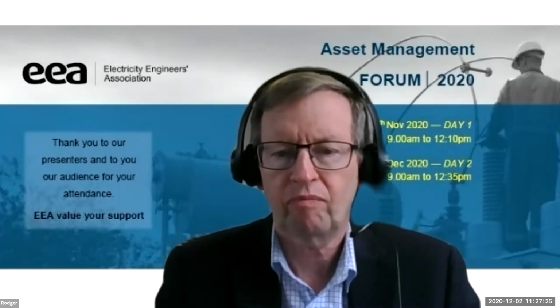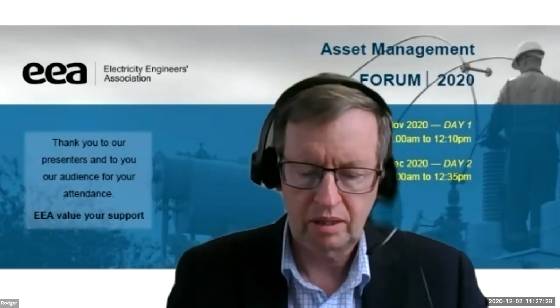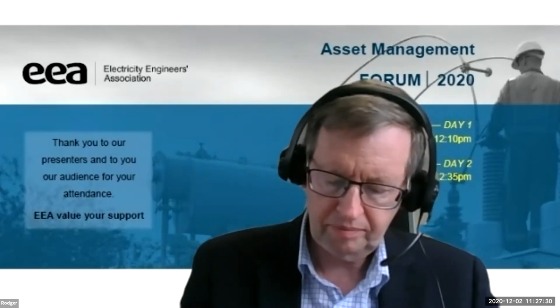Yeah, so in Australia, I think an SCR of less than 3 is considered to be very low, and that's where the threshold is set in terms of having to provide a system strength remediation scheme. Anything higher than that, if you can demonstrate through system studies that you will not have an adverse impact or do no harm to the system, you've got more justification to not provide any remediation schemes. But yeah, I think SCR of 3 is definitely the industry's threshold.